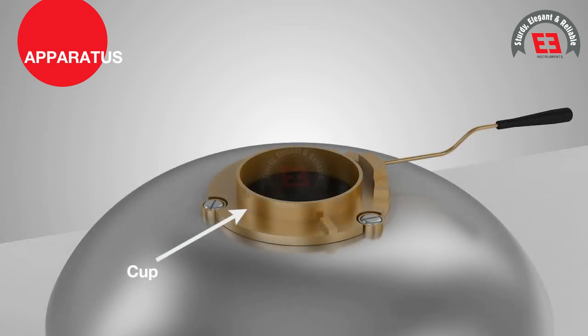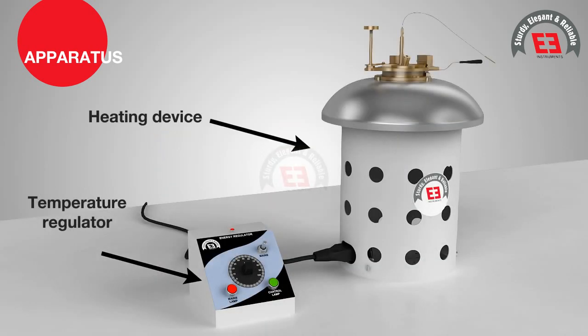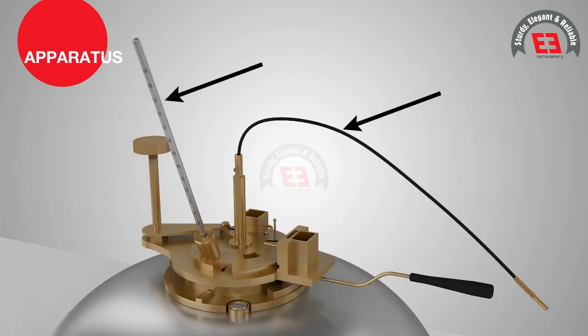The Pensky-Martens Closed Cup Tester consists of a cup, flame exposure device, heating device with temperature regulator, stirring device, and suitable thermometer.